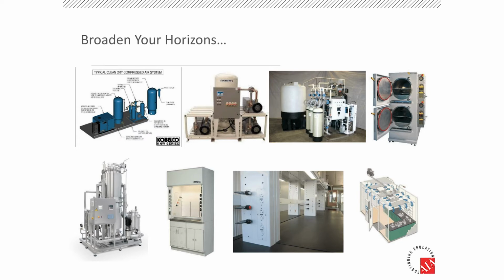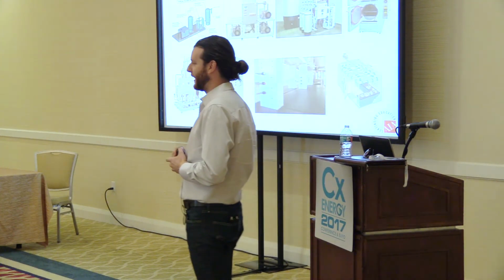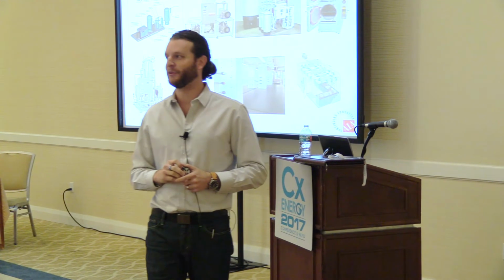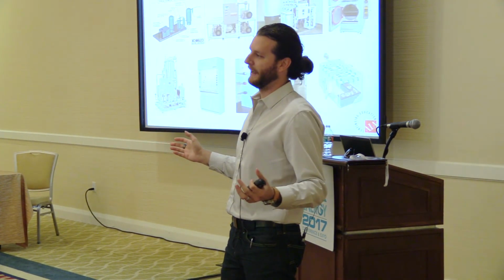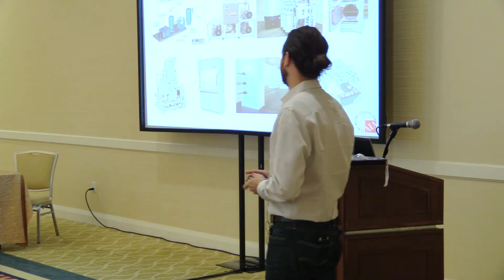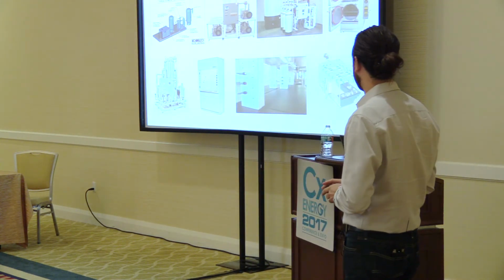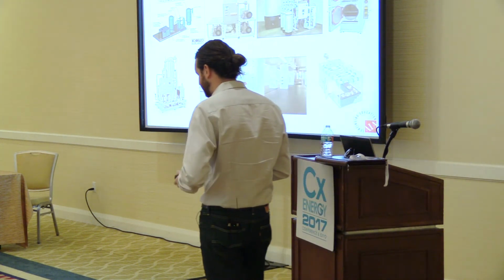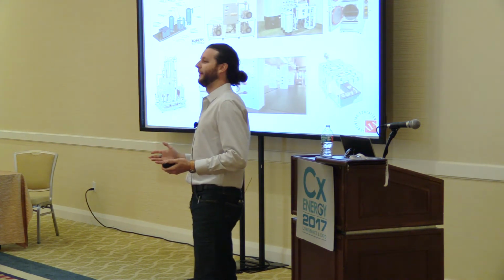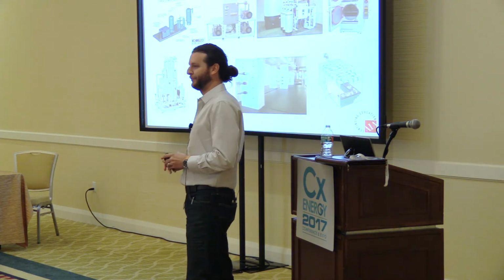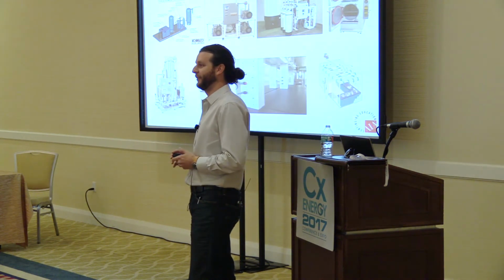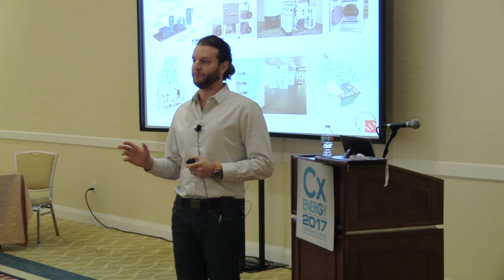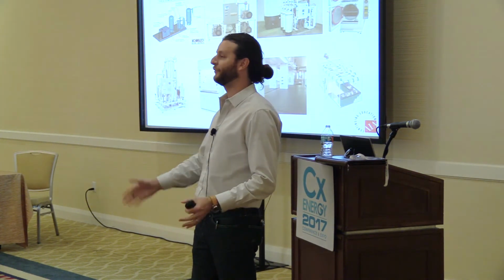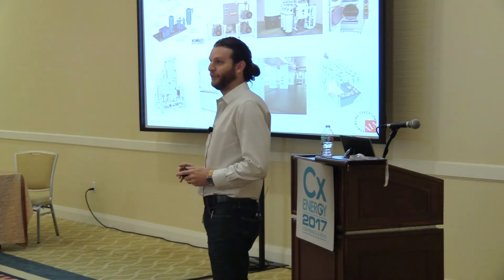Big picture of this presentation, I could get into tons of case studies, but at the end of the day, it's all about broadening our horizons. There are a lot of systems that we commission that are outside your typical MEP, and we find tons of issues with them. I'm sure that's no surprise. But the difference is, you might say, I got this RFP, and all it says is I have to commission the mechanical systems. Well, yeah, that's true, but that doesn't stop you from teaching your client. Put a line item on your proposal that says, in our experience, this is great, but you should also commission these 10 systems because we've seen tons of failure rates with them, or they're highly critical, and we should be commissioning those.